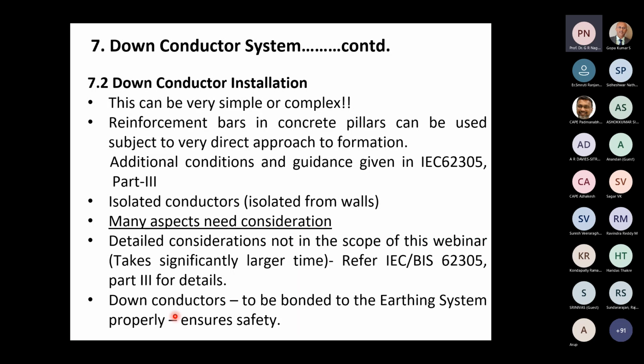Now, the next important thing: the down conductor has brought the lightning current down to the earth level. Now it has to be transferred to the earth in a very safe way and distributed in a very safe way. Both are very important. One small point which I have missed mentioning is that, to study the effectiveness of the earth resistance, there must be a joint between the down conductor and the earth system which can be separated to measure the earth resistance independently. This is a very important point, which I will try to remember and mention once again.